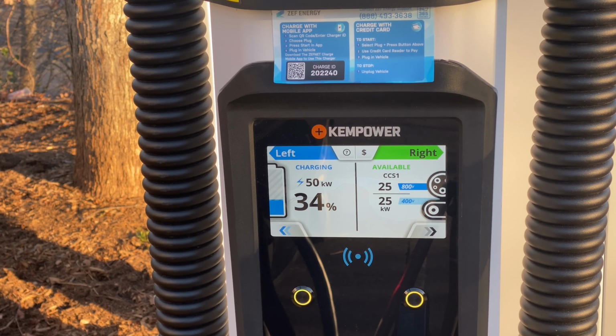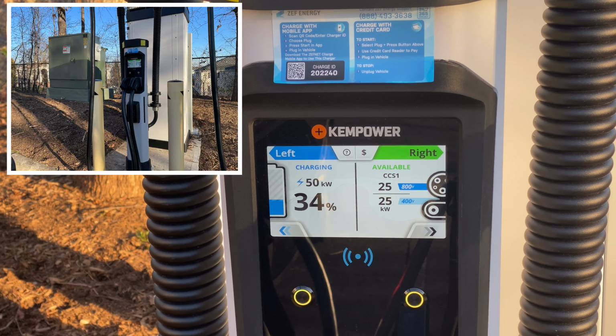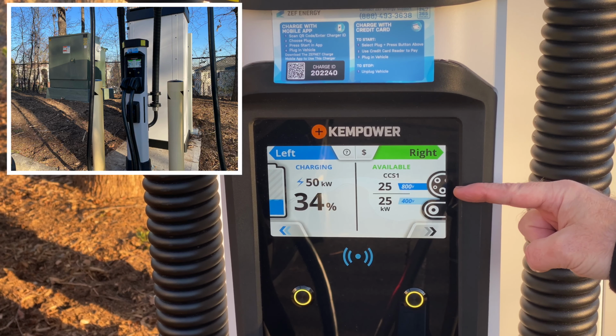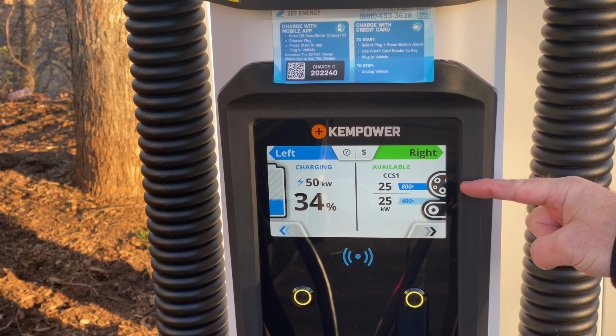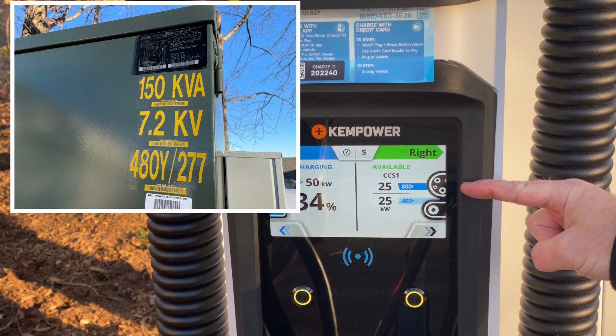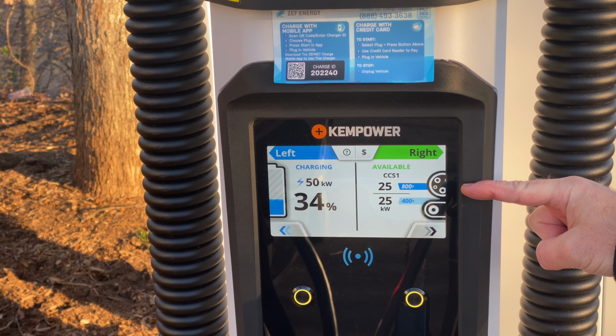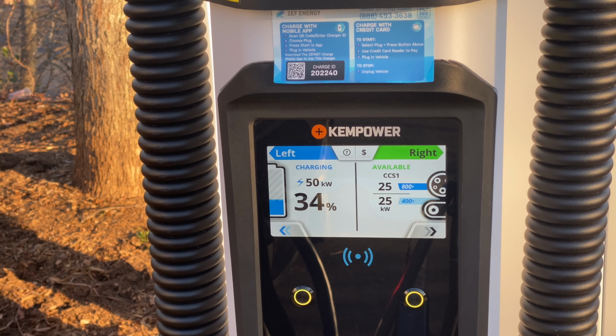Now, this power unit probably only has one power module in it, which is why it's only doing 50 kilowatts. The transformer over there is 150 kVA, so this site just isn't designed to output what this hardware is capable of — but it's still very reliable hardware. That's the nice thing: it's flexible. You can scale out as your site increases.